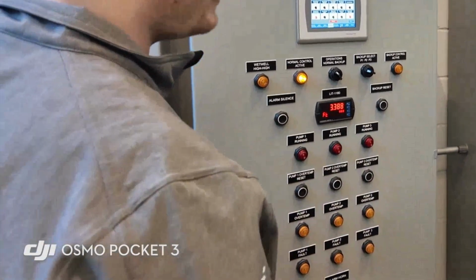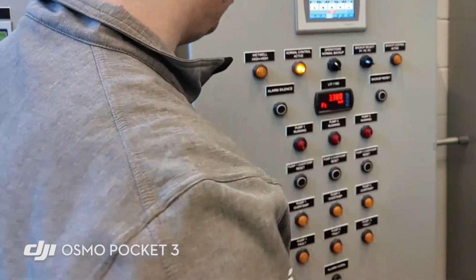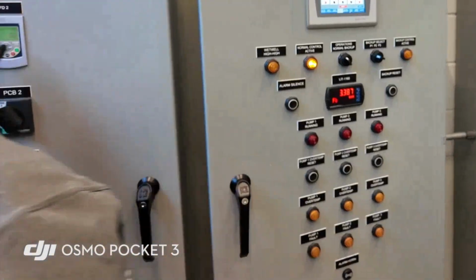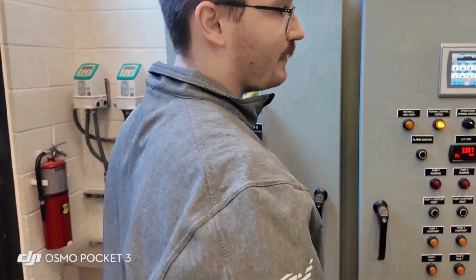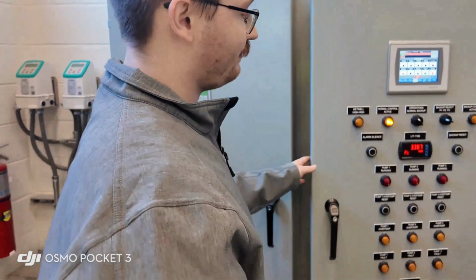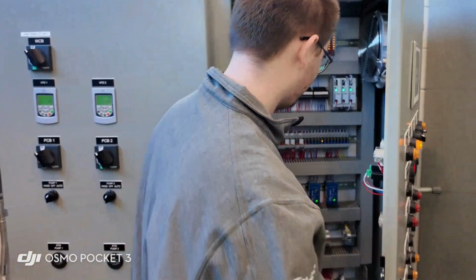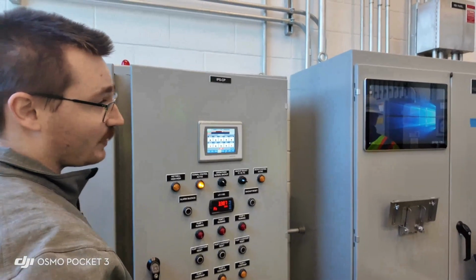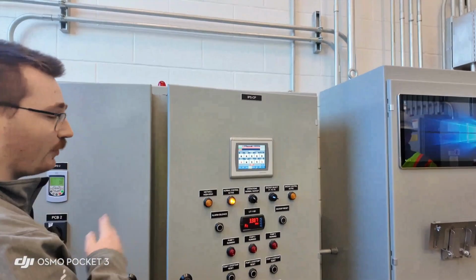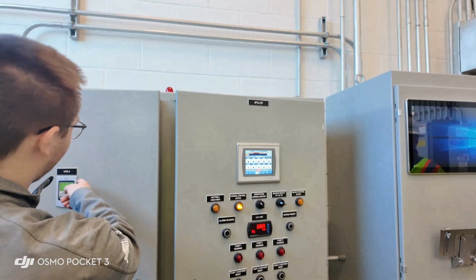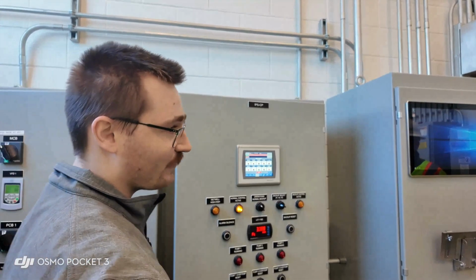So to determine which common fault it is, we've got the overtemp. There'll be an FO code on the HMI, and for seal, you have to open it and check, see if it's a seal indication in here. Overtemp will shut down the pumps. The common won't shut it off. It's only if there's a fault on the drive itself, or if there's an overtemp, that's what's going to stop the pump.